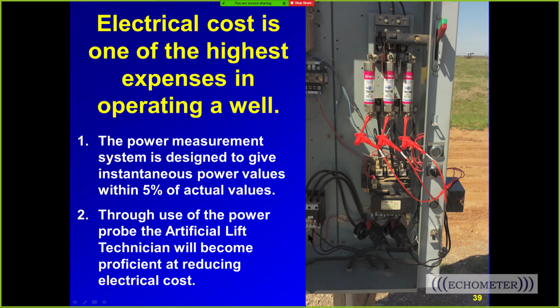This is the same slide I had at the intro of the other presentation, and I'm a big proponent of measuring motor power and measuring the power during the stroke and using that information to analyze the well. Why are my motors burning up? Why are my efficiencies low? What bearings are bad? Do I have a bad bearing? Why is my power bill too high? All those questions can be answered with this equipment. Ever since I've been around the well analyzer, I've been promoting using the power probe. It's something that's a really valuable tool.